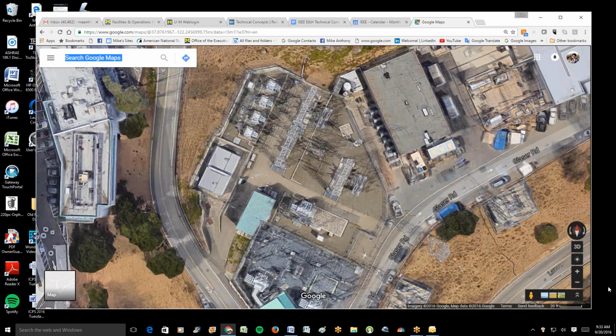Well, I would say that the bank of single-phase transformers would give you a lower reliability, because you're looking at a much larger infrastructure to take into consideration, which is the cables and the connections and everything else that's going on. But I also think the three-phase would give you a little higher availability and reliability number, but your efficiency should be much higher in a single three-phase than in individual single-phase transformers. That would be my gut feeling without looking at the exact load characteristics.